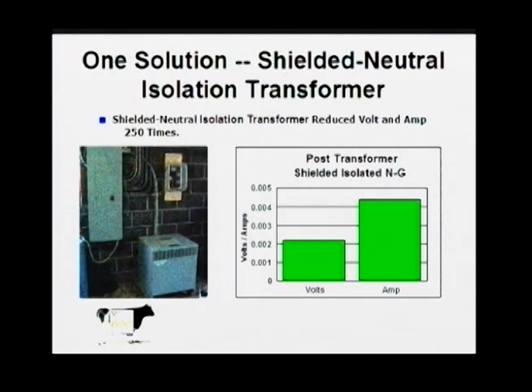Installation of a shielded neutral isolation transformer between utility power supply and dairy farms reduced radio frequency EMF to near zero and allowed performance of damaged herds to return to normal after several months of recovery. Isolation of farms by moving the transformer pole from the barnyard was helped in some locations. EMF radiated from overhead lines can be reduced by engineering determination. Capacitive filters tuned to the prevailing frequencies can reduce EMF in the living environment.